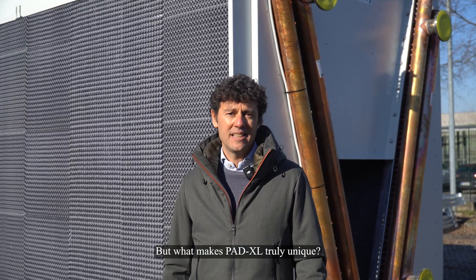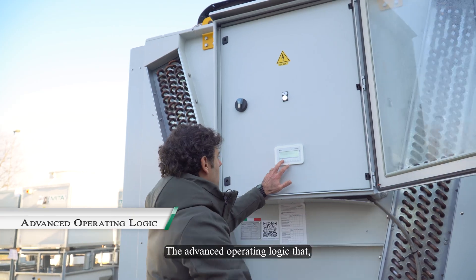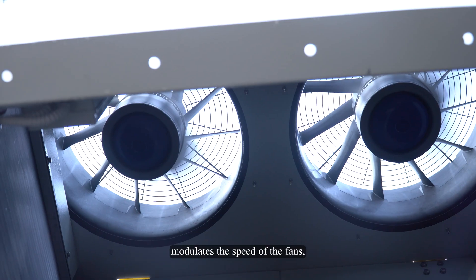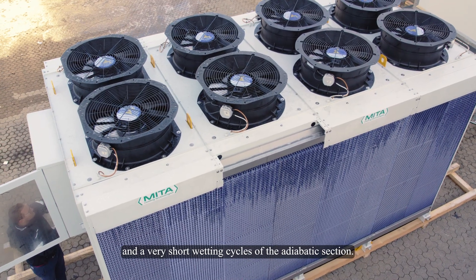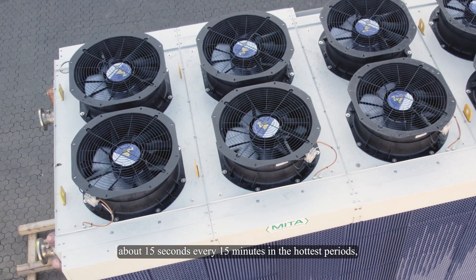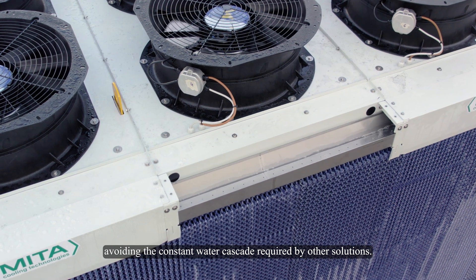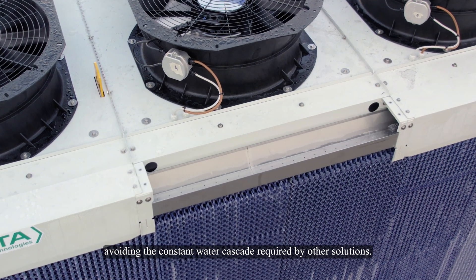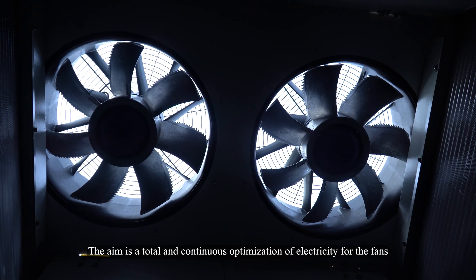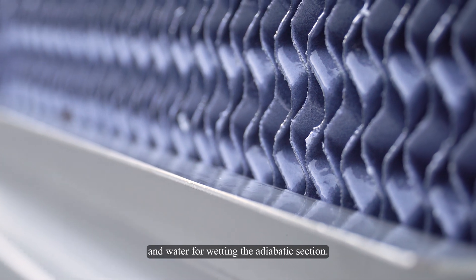But what makes PAD-XL truly unique? The advanced operating logic that, together with various sensors and a specific regulator, modulates the speed of the fans and the very short wetting cycles of the adiabatic section — about 15 seconds every 15 minutes in the hottest periods — avoiding the constant water cascade required by other solutions. The aim is a total and continuous optimization of electricity for the fans and water for wetting the adiabatic section.